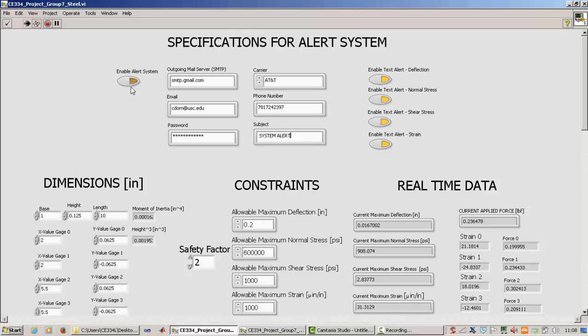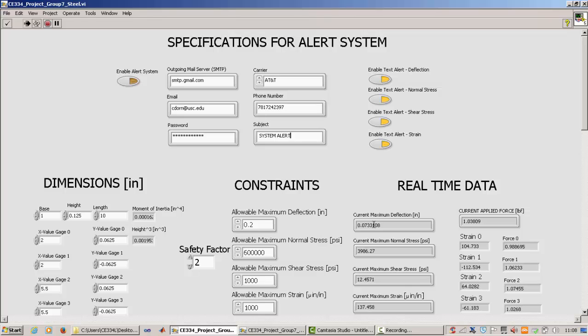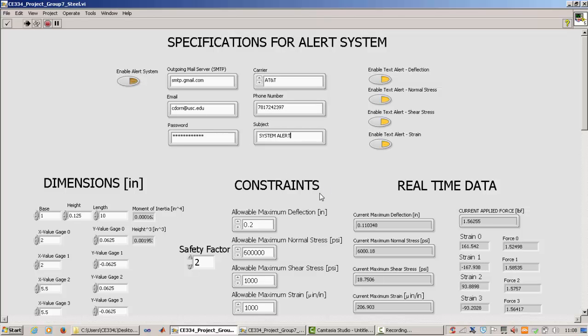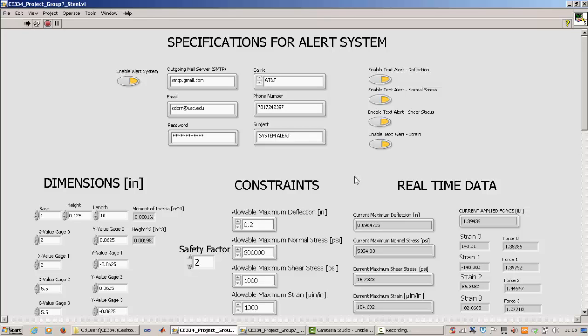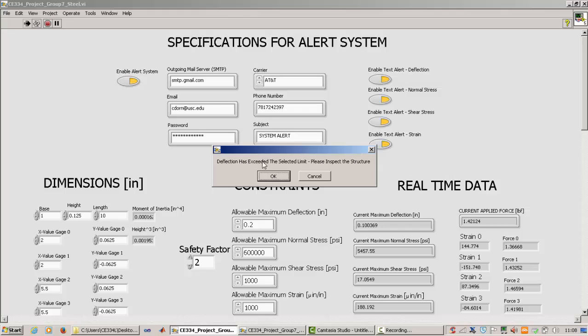And so right now the alert system is off, which is good because let's apply maximum deflection of greater than 0.1. So right now it's greater than 0.1, and we didn't get any alert messages, which is good because it's off. So now I'm going to put it back down a little bit. So now it's below 0.1. So when I turn this on, it's not going to give us a message right away. But right after I go above 0.1, we're going to get a message on the screen. And I'm also going to get a text sent to my phone. So as you can see, immediately as I reach 0.1, it's going to tell me deflection has exceeded the selected limit. It's going to tell me to inspect the structure.